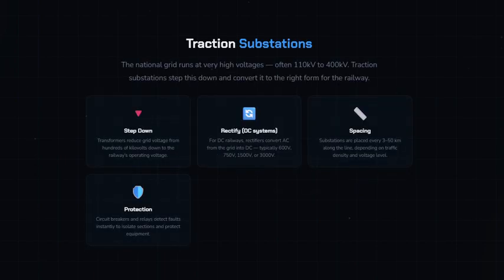Traction substations are the link between the national grid and the railway. They take grid power, often at 110 to 400 kilovolts, and step it down using transformers. For DC railways, rectifiers convert the AC into direct current, typically at 750 or 1500 volts. These substations are spaced every few kilometers to tens of kilometers along the line, and they include circuit breakers and protection relays to isolate faults instantly.